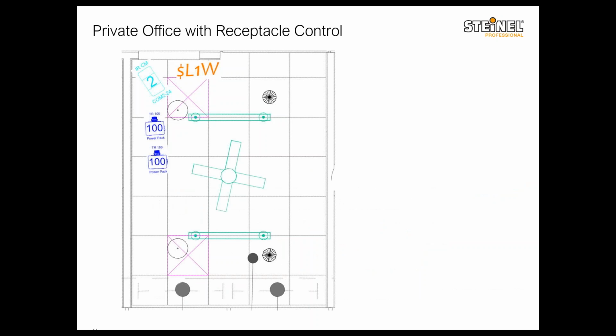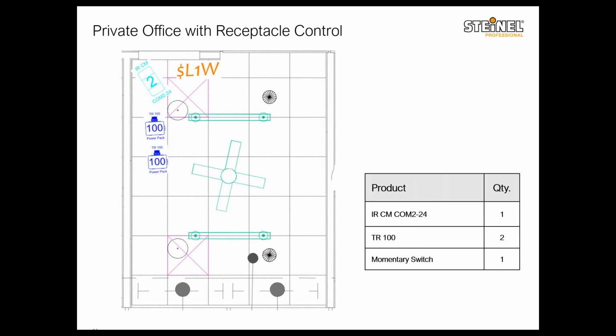So as you can see, this is the same small office, same sensor, and pretty much the same thing. You just need to add one more power pack to the mix, and the second power pack would be controlled by the HVAC output. So that would be an auto-on situation, that as soon as you enter, there is occupancy in the room, plug loads will be turned on. I mean, the controlled plug loads will also turn on, and then will turn off on a separate timer from the timer for lighting. So if your lighting control is set to 15 minutes, your plug loads have their own independent time delay.